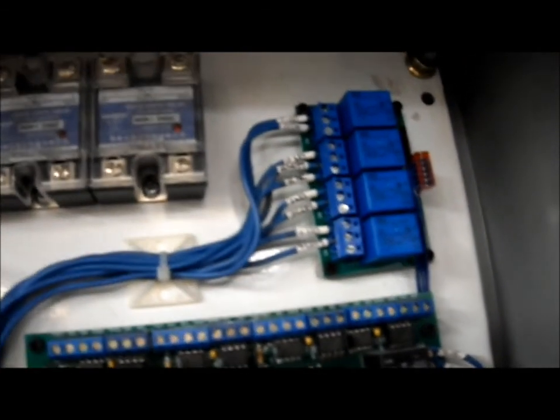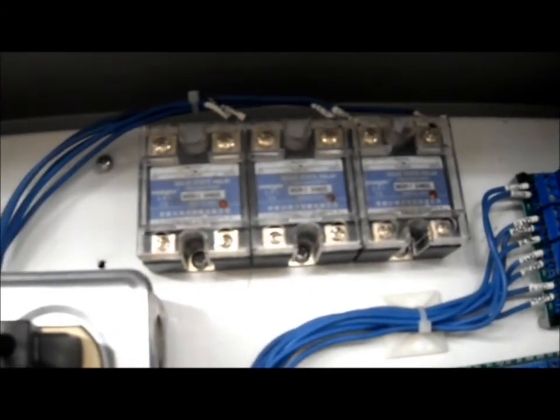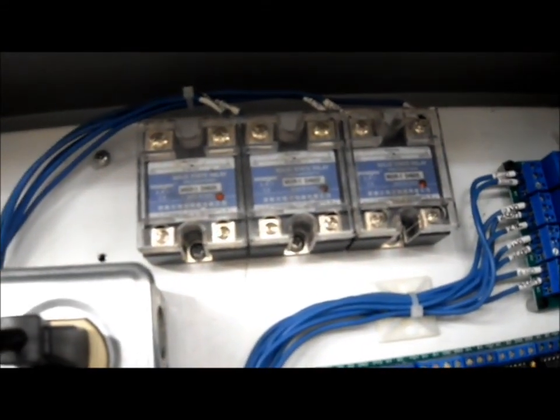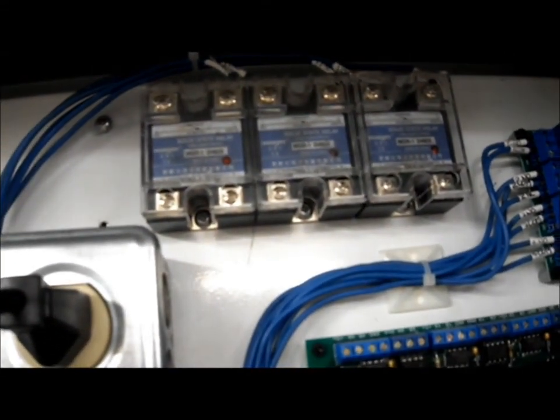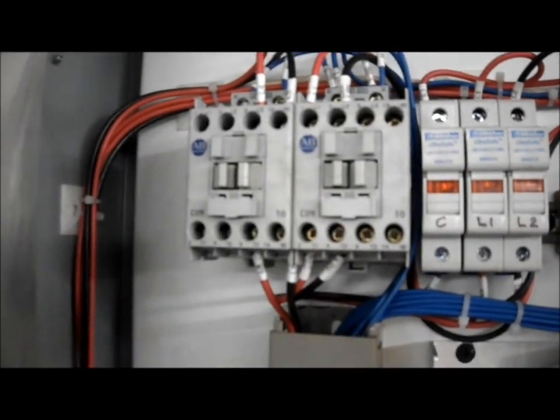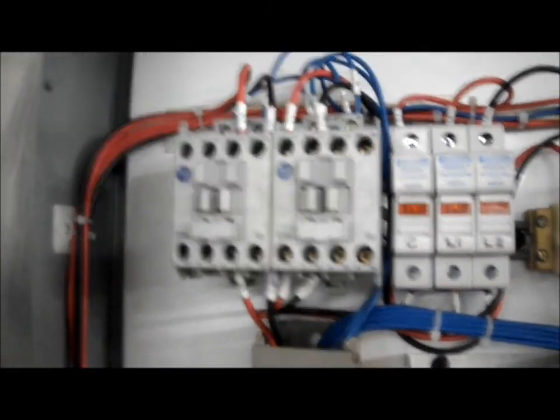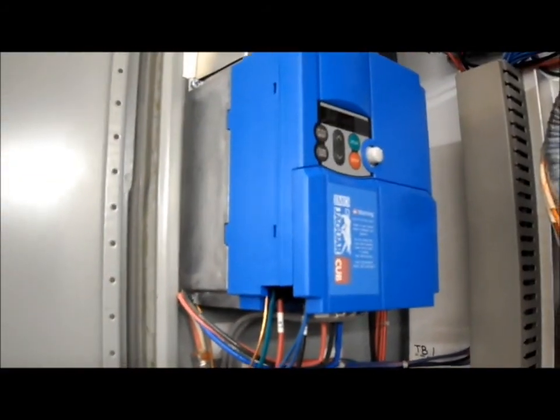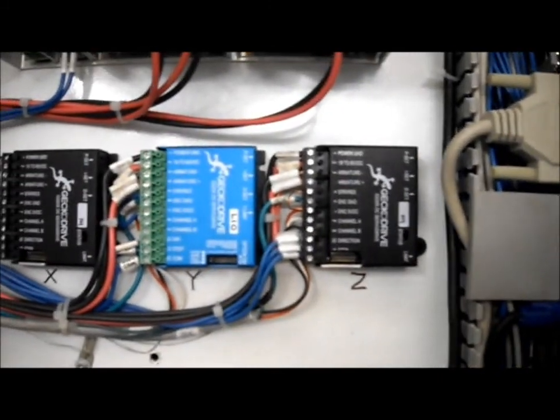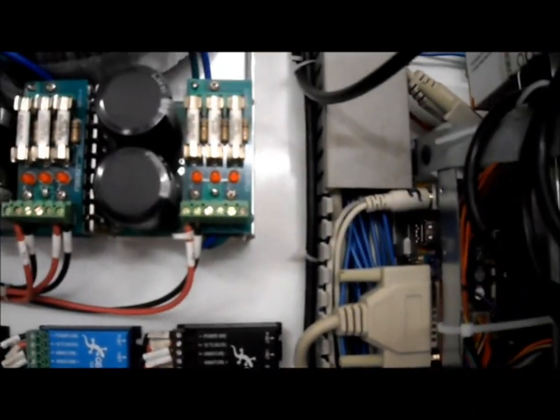These electronic relays, I tried to use them for the contactor, but they failed in the on position, so they're there but they're not being used. And what I did is I went back over to these ones, Allen Bradley contactors, one for the power supply right here, and the other one for the variable frequency drive. And there's the geckos again, and you can see how they're labeled, the Z, the Y, the X. Everything's labeled so you have an idea if you're going to troubleshoot and where you're going to go.